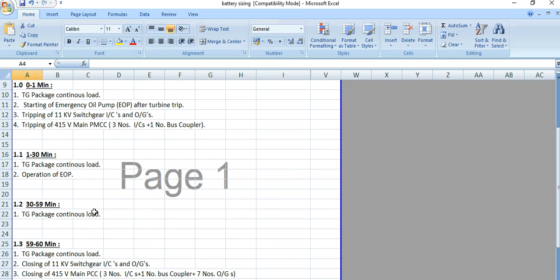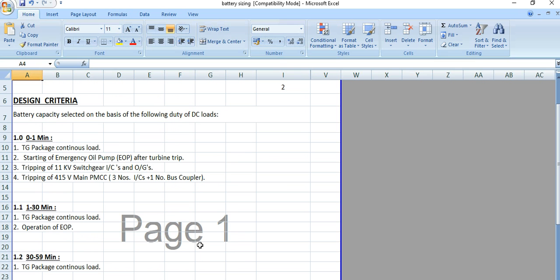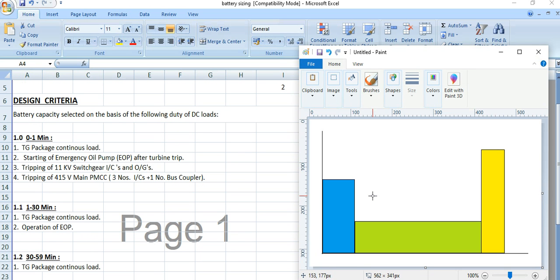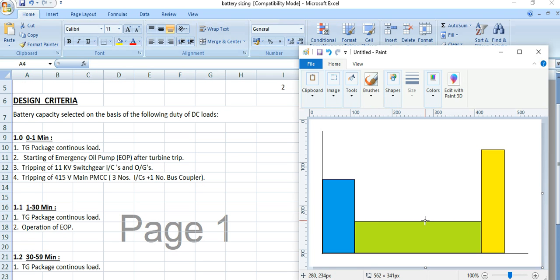Looking at the typical load cycle figure: the first section is the one-minute load, which the battery needs to provide DC supply for. Then from one minute to 59 minutes is the continuous load. And finally, the last minute load is the 59 to 60 minute load profile. This is the DC load profile that the battery needs to supply.